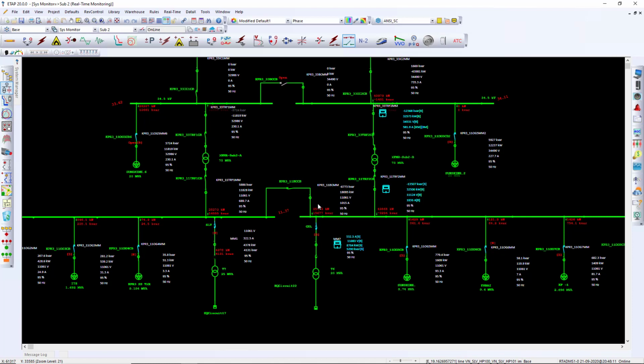The nice thing about having it in ETAP is that from here I have a full-fledged set of modules, for example, switching sequence management. I have full management and service restoration. I have the load flow calculations, short circuit calculations, arc flash calculations, all of that available to me, where I can use real-time data and perform quick calculations. So over 100 modules that can utilize real-time data are available within the ETAP station.